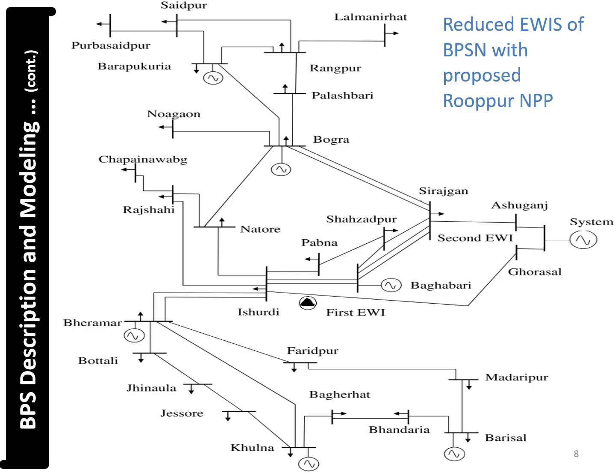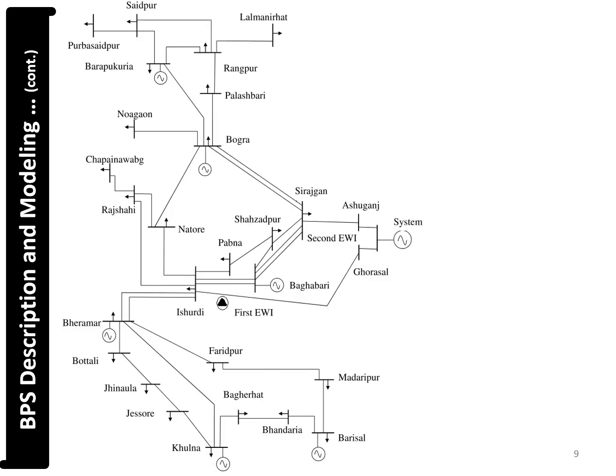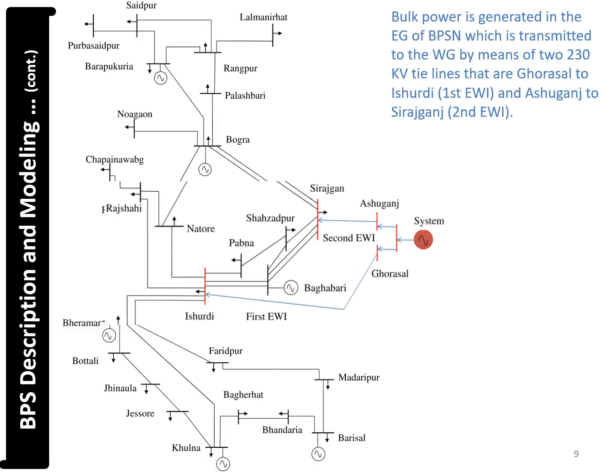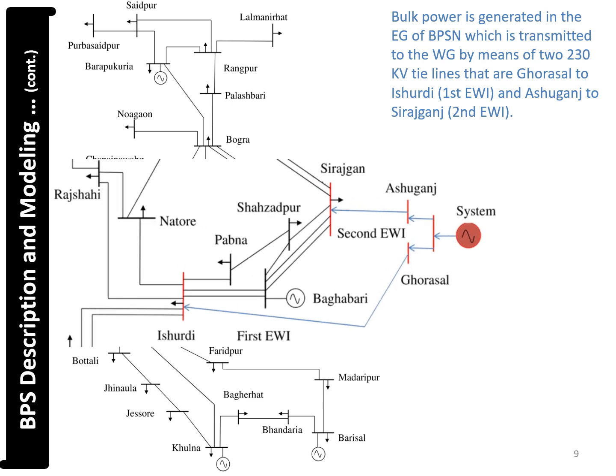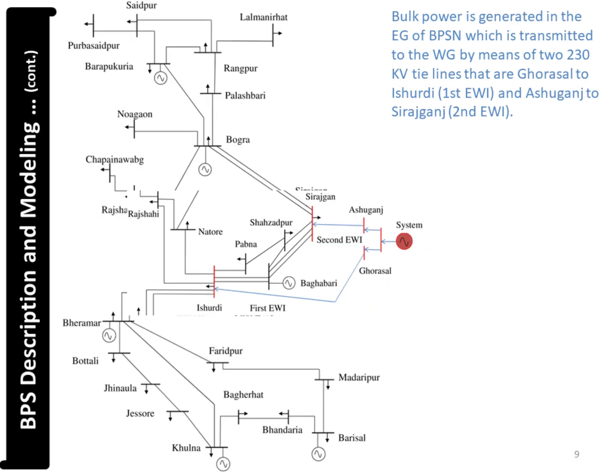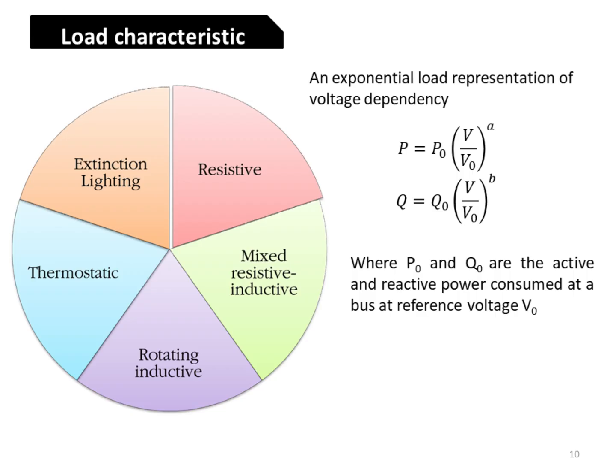This slide shows the reduced east and western interconnection system with Rooppur NPP integrated. The 2 critical tie lines are highlighted. Bulk power transfer from the eastern to western grid is essential for maintaining voltage stability near Rooppur. Load behavior is modeled using exponential voltage-dependent equations. Active and reactive power at a bus depend on voltage exponents A and B. This representation helps simulate how voltage drops affect load demand and system stability.